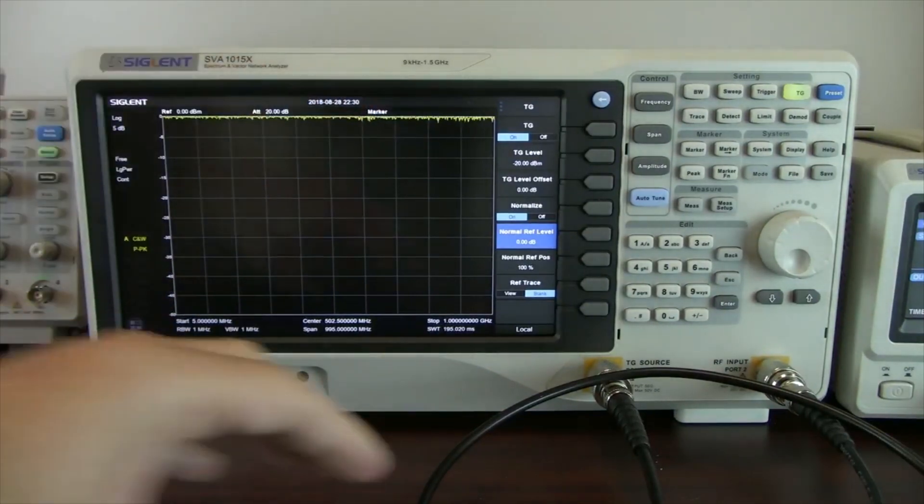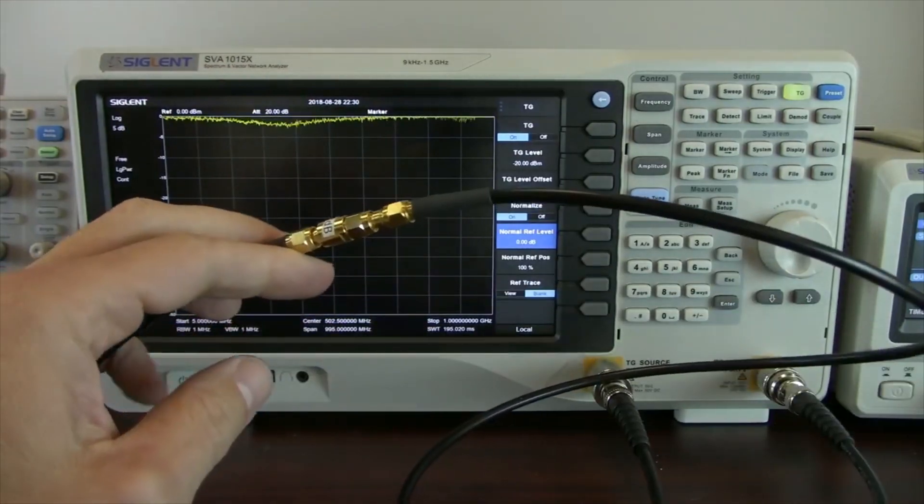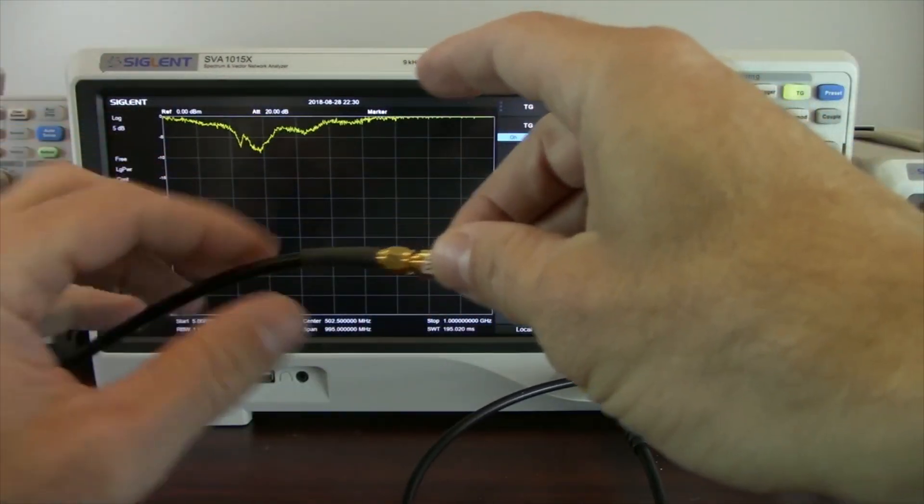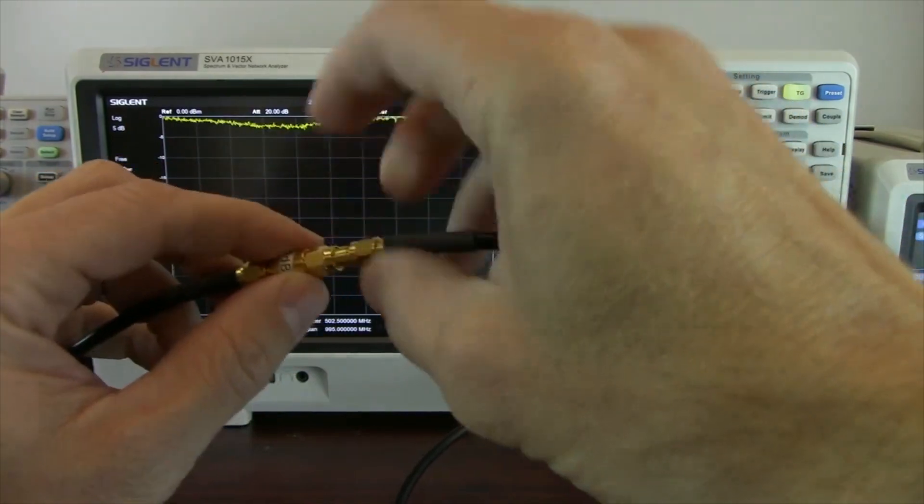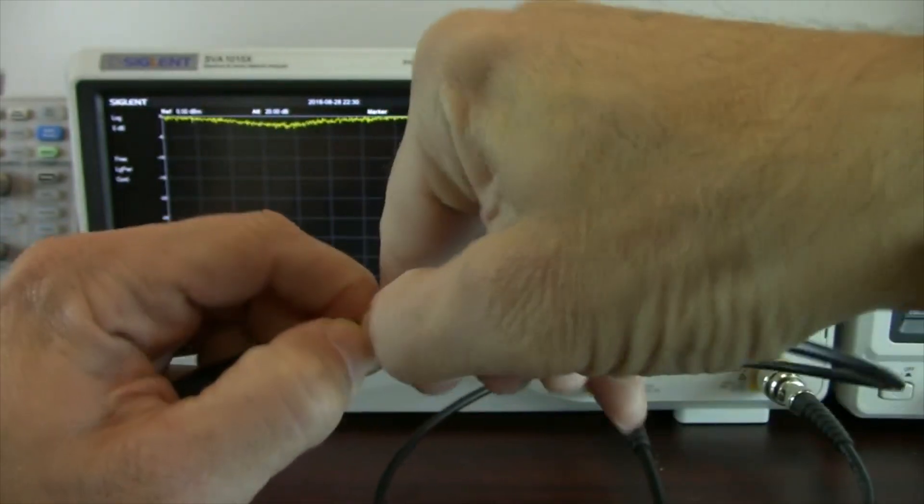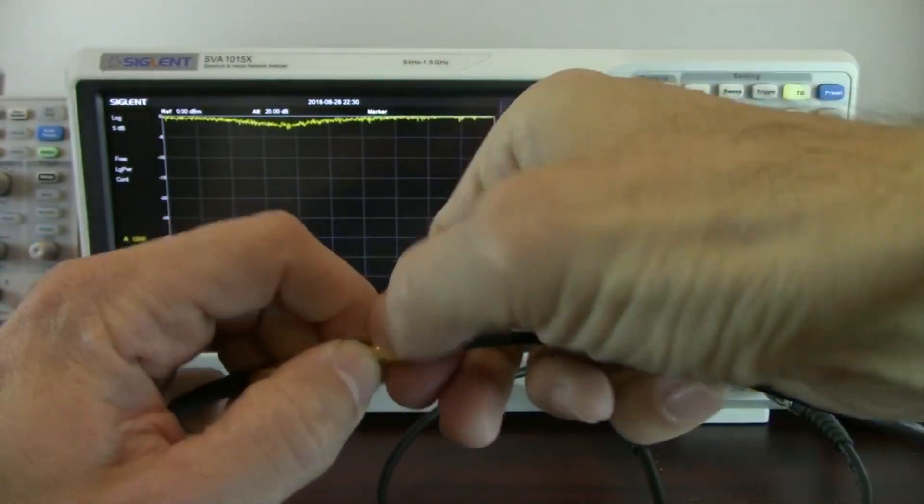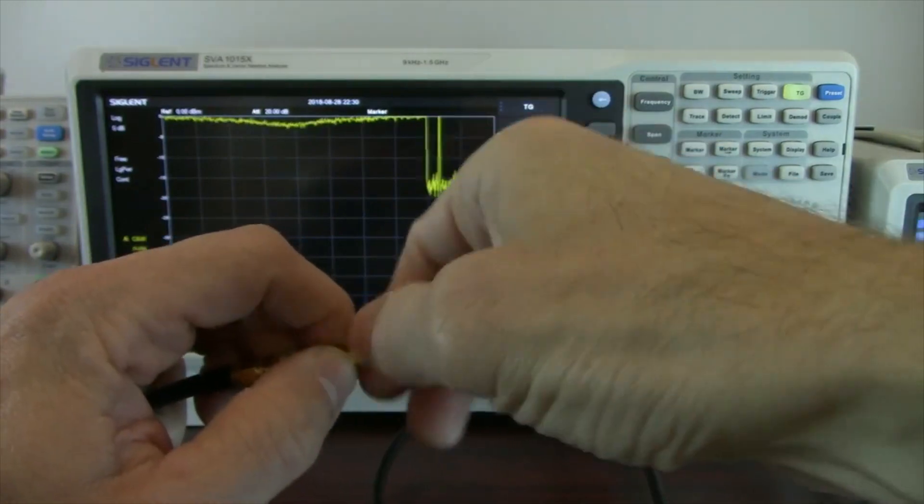So now we're making relative measurements to that original input. We actually have minus 20 dB minus another 20, so minus 40 dB, but we're removing all of that mathematically. So everything we measure after this, all the measurements are going to be relative.